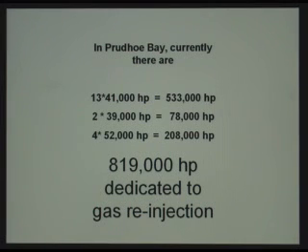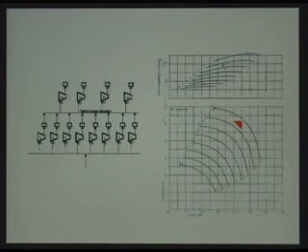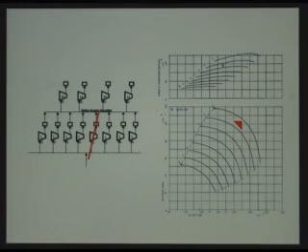Since that is directly related to the revenue stream, those machines are run at max speed, max power all the time. So these 12 machines, the low stage machines, were operating at maximum power that's available for the day, almost at their maximum speed. And an instrument tech came in and had to do a little bit of work on one of the control panels. And so he went into the control room, opened the control panel, started doing his tests, and unfortunately he crossed a circuit where it shouldn't have been, and so that machine immediately tripped offline.